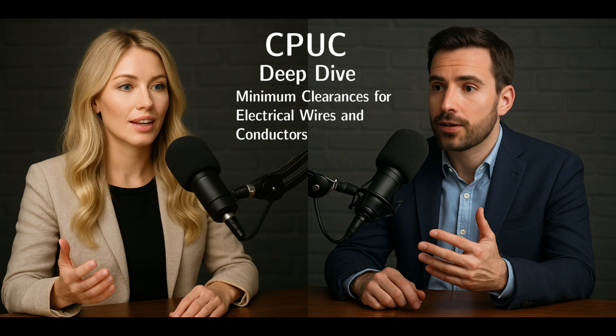Got it. And even horizontal clearance, like how far a wire just hanging there at rest needs to be from a building it's not attached to. Okay. That ranges from just 3 feet for, say, a communication cable up to a pretty significant 15 feet for those 300 to 550 kV lines. 15 feet away horizontally. Yep. And even the distance from the pole itself is specified, like 15 inches from the center line of the pole for comms wires, or just 3 inches from the surface of the pole for many power lines. Wow, down to the inch.